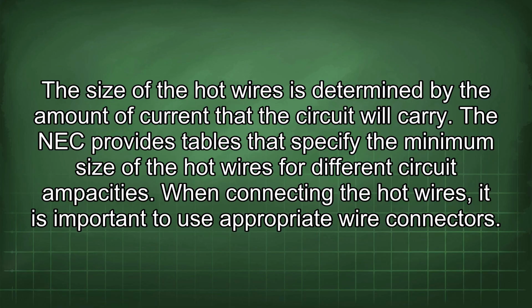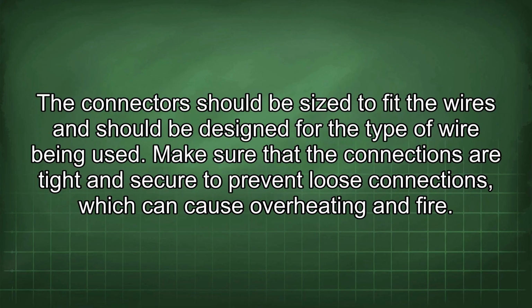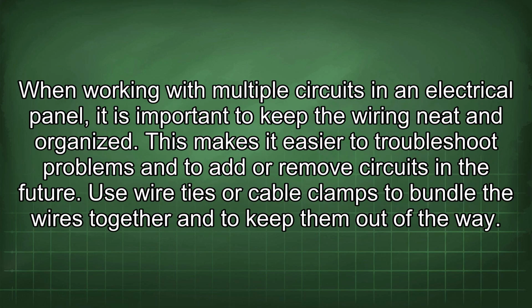When connecting the hot wires, it is important to use appropriate wire connectors. The connector should be sized to fit the wires and should be designed for the type of wire being used. Make sure that the connections are tight and secure to prevent loose connections, which can cause overheating and fire. When working with multiple circuits in an electrical panel, it is important to keep the wiring neat and organized. This makes it easier to troubleshoot problems and to add or remove circuits in the future.